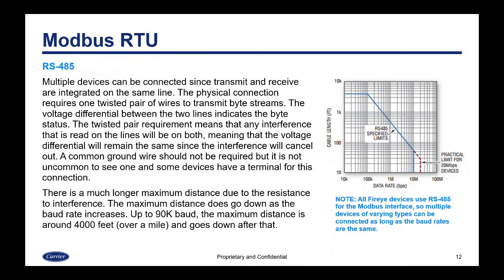Next we have RS-485. Multiple devices can be connected since transmit and receive are integrated on the same line. The physical connection requires one twisted pair of wires to transmit byte streams. The voltage differential between the two lines indicates the byte status. The twisted pair requirement means that any interference read on the lines will appear on both lines, so the voltage differential will remain the same since the interference will cancel out. A common ground wire should not be required but it is not uncommon to see one, and some devices do have a terminal for this connection.